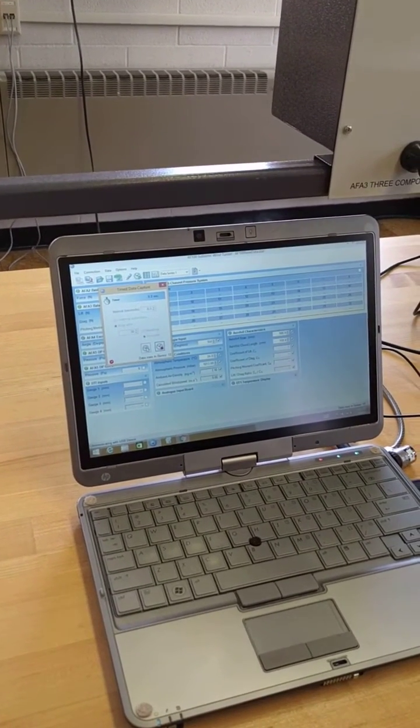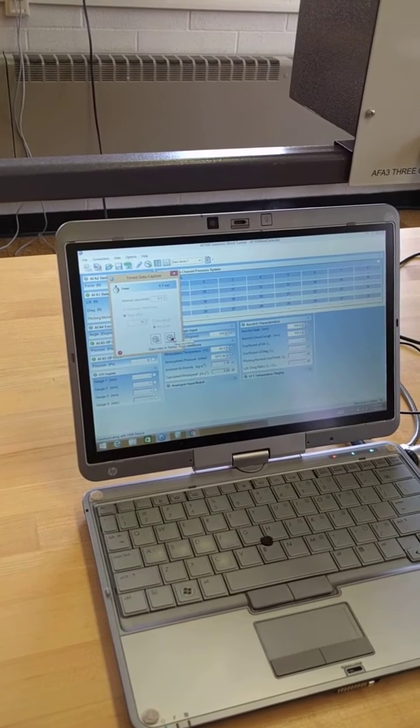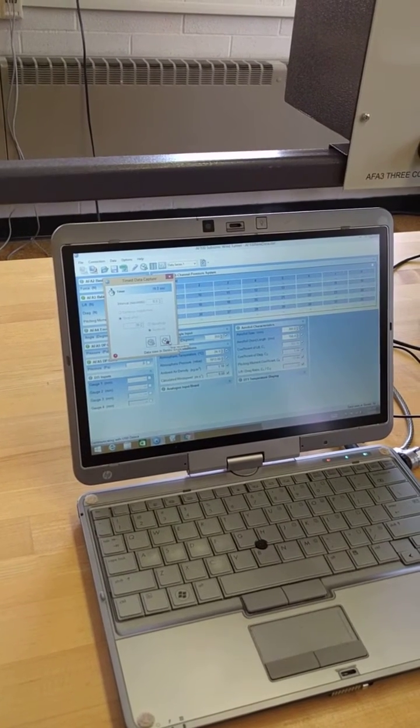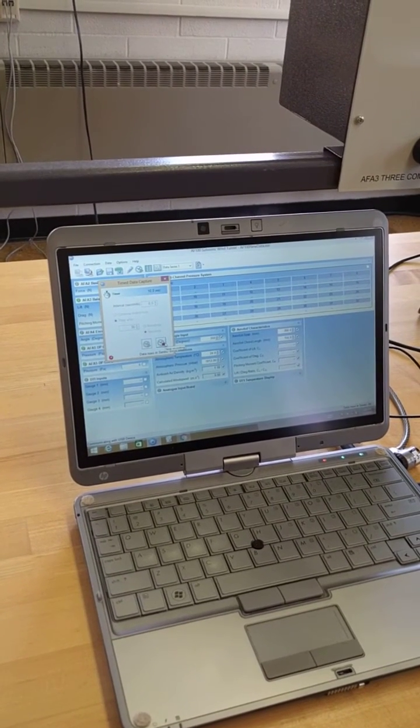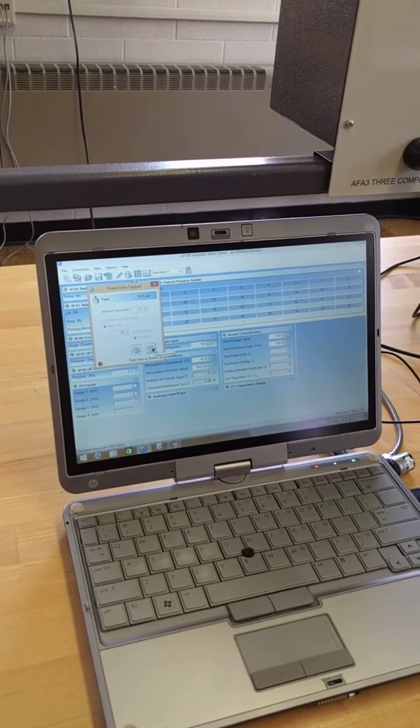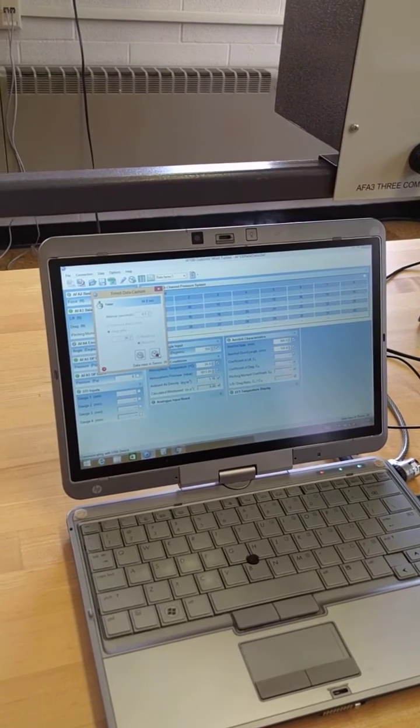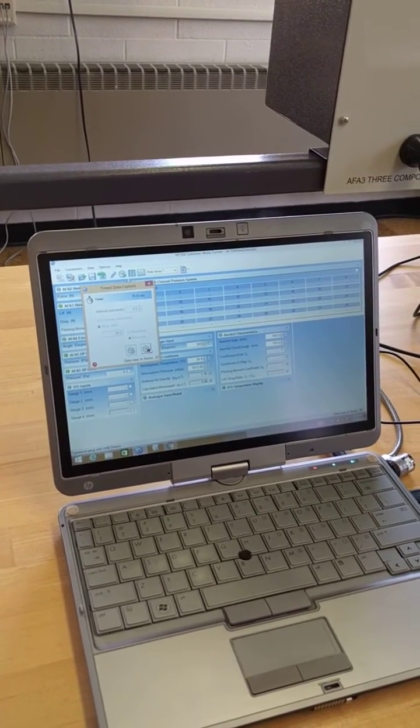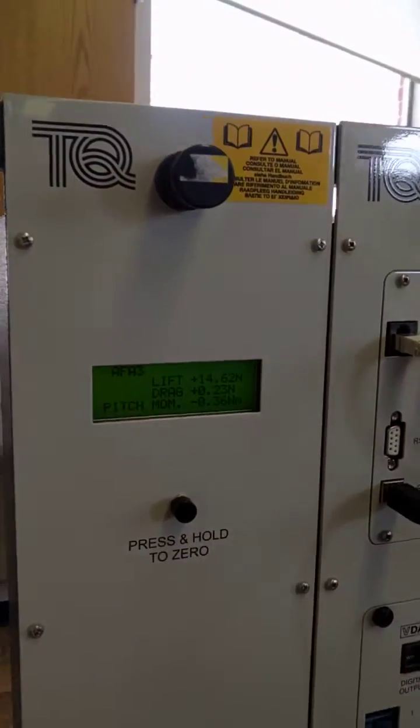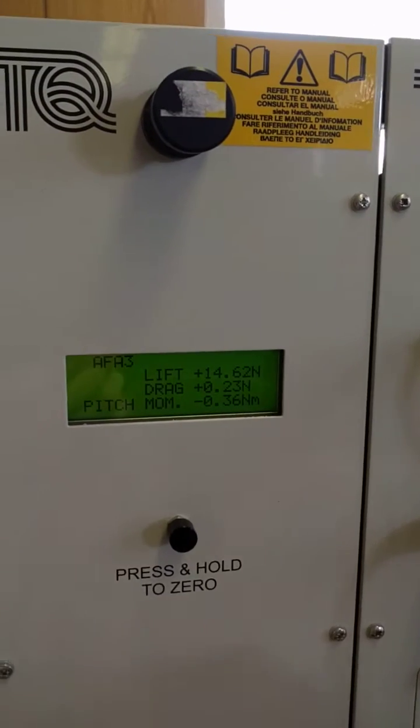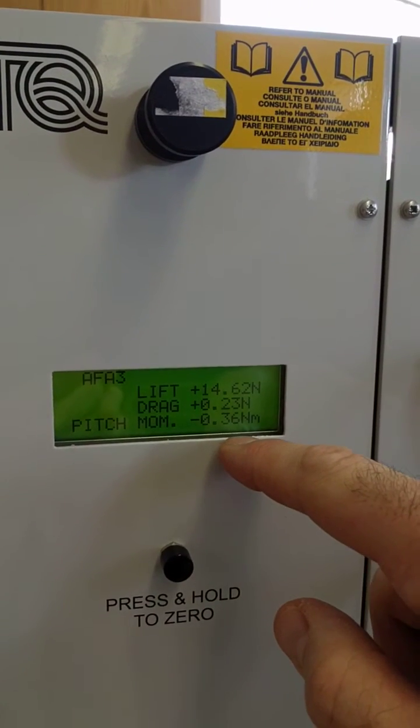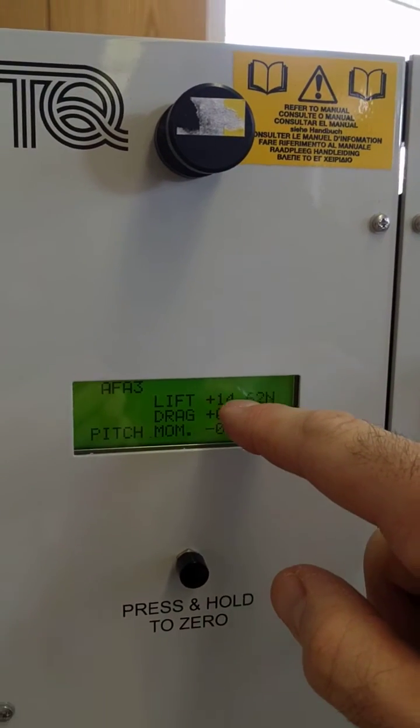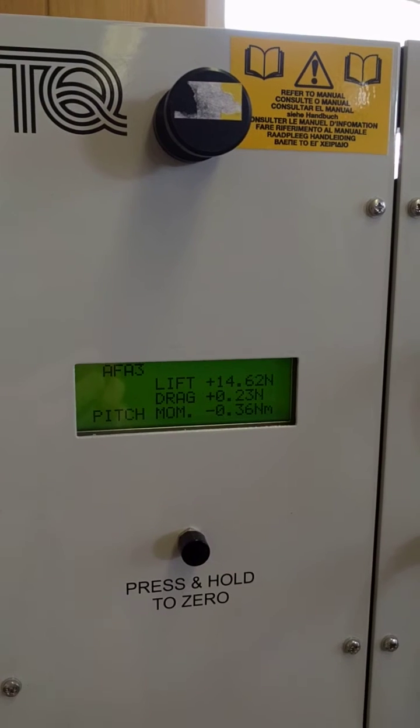Now as that's recording, I need to mention one thing that I had forgotten to mention beforehand. Before you start collecting any data, you need to zero the force transducer. If you look right now, the force transducer digital readouts give you lift, drag, and pitching moment other than zero.